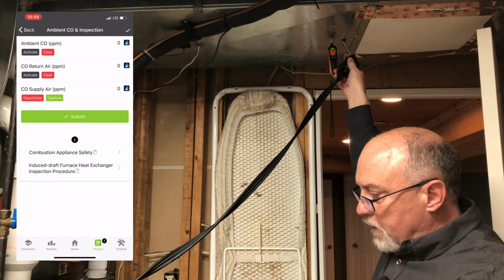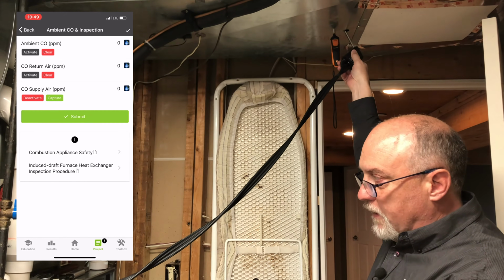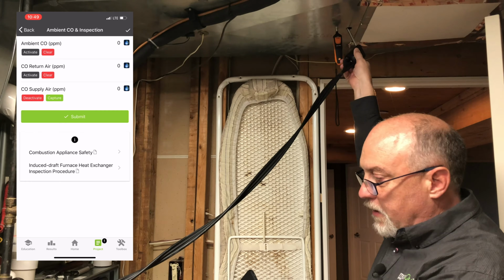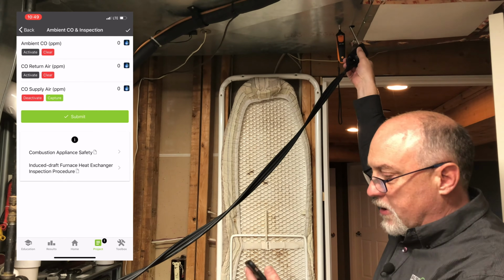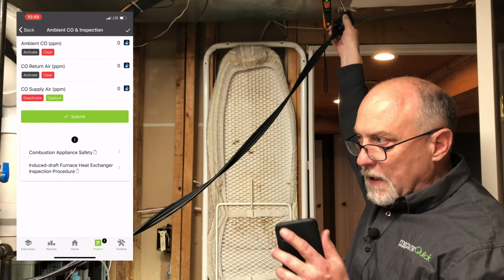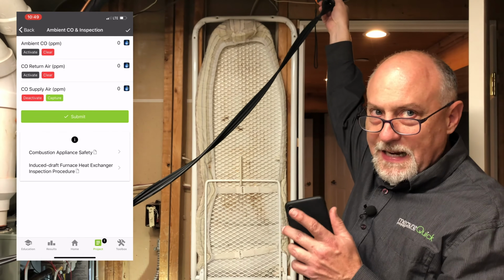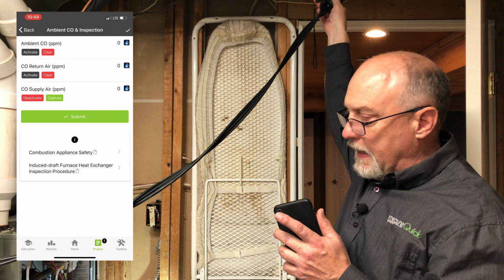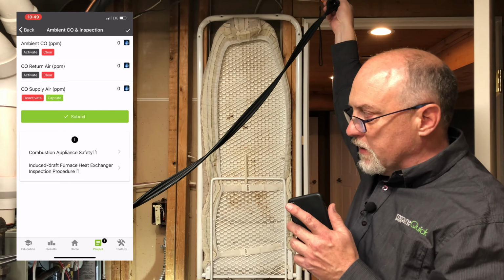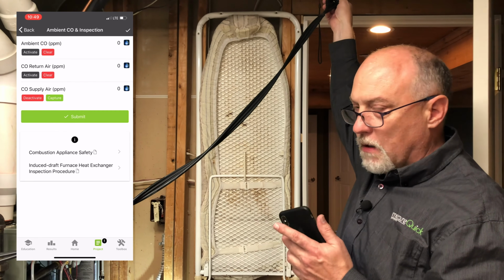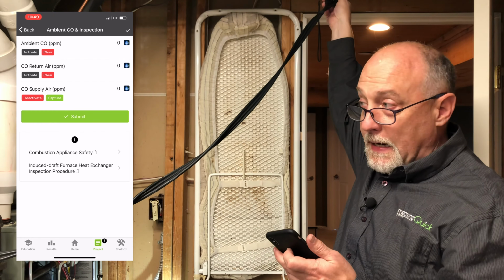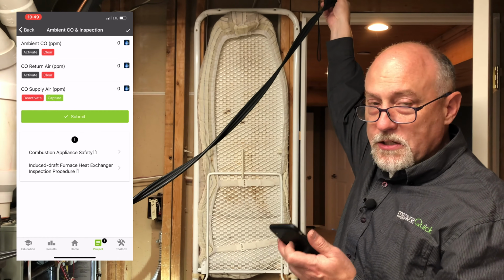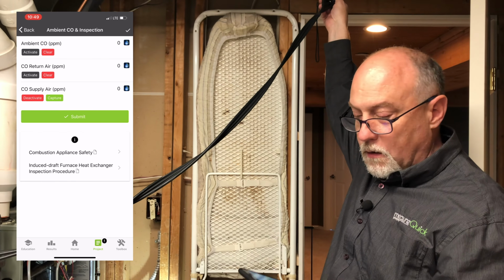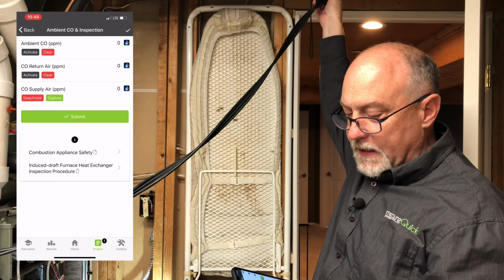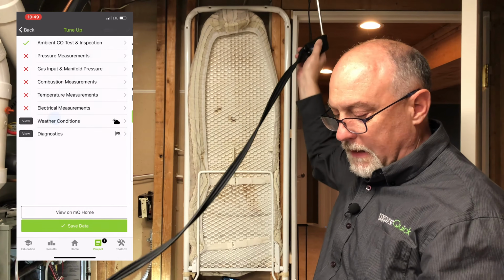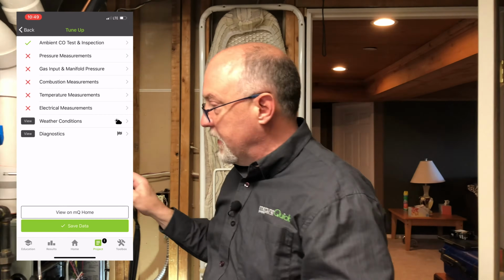If we know we have a small amount of CO being produced by the furnace, and if there's any breach in the heat exchanger in any way that flue gas is getting into the airstream here, we'll pick that up. Now it's really important to use a combustion analyzer to do this test. You do not want to use a standard CO meter, because a lot of them are not temperature compensated. When you get the hot air in here and it changes the temperature of the meter, it could give you false CO on there. And again, this is good, so I'm going to hit capture, and I'm going to hit submit, and now I've got my ambient CO measurements in here.